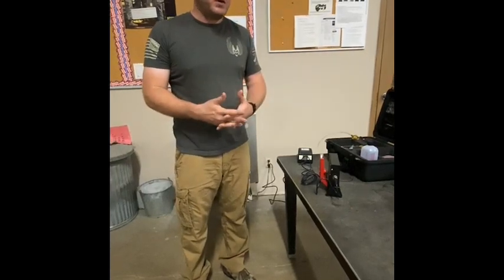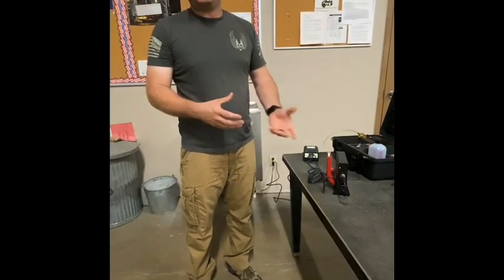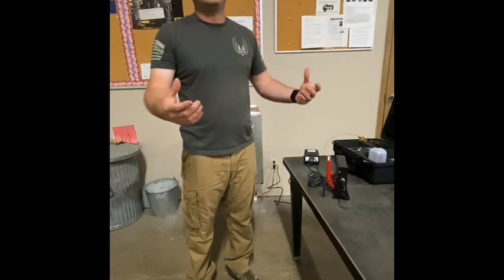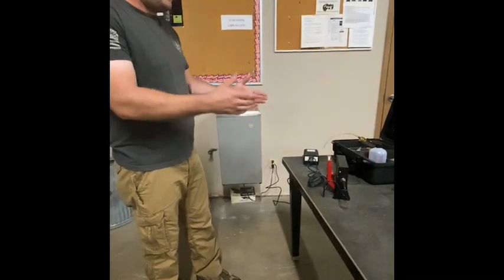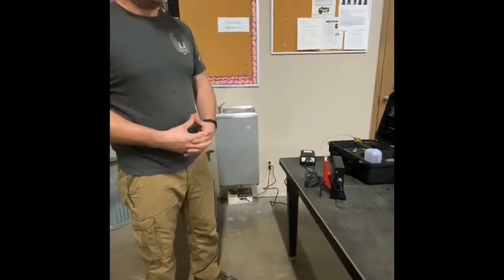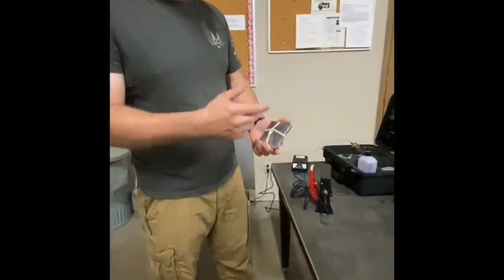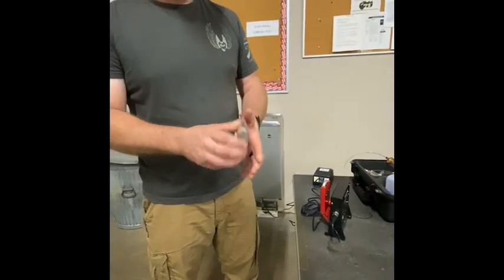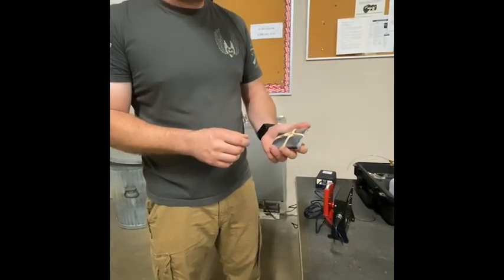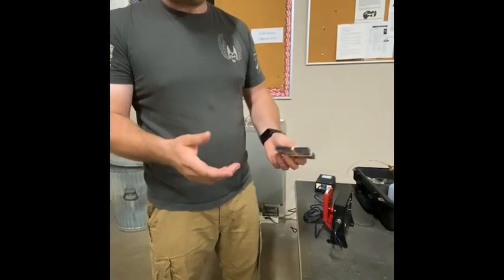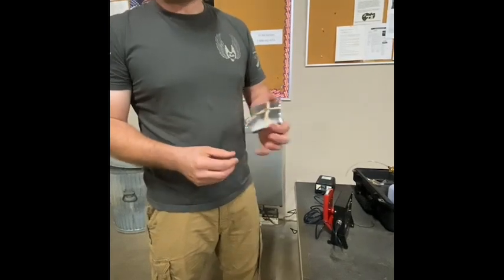I know from experience that sometimes these systems, you think that they're completely sealed, but sometimes they pull moisture into the system from the area surrounding the system. We did have issues with that. So that is the basic fuel sample procedure. After you have your pad tested, you would take that sample pad, put it back in the envelope that it came out of, and write on it how many parts per million, date, possibly time. That might be part of the procedure itself. But after that, file it or do whatever the ROE calls for, and that is your fuel sampling process.